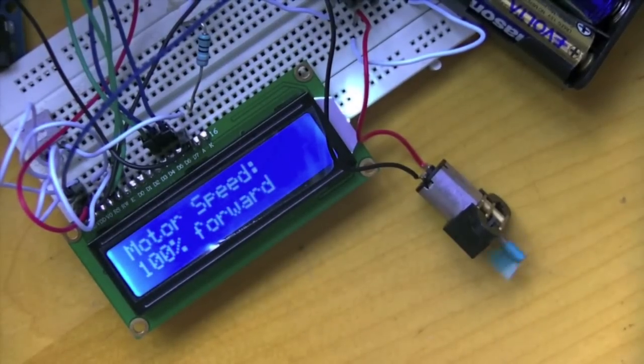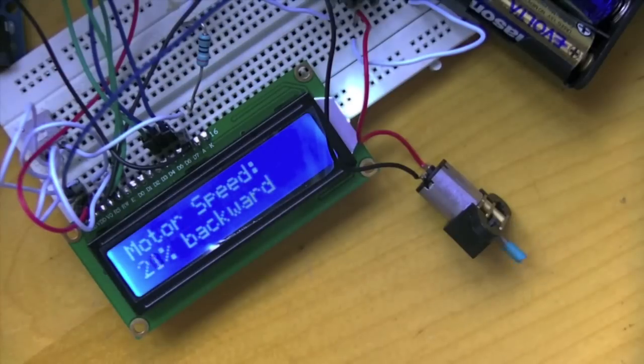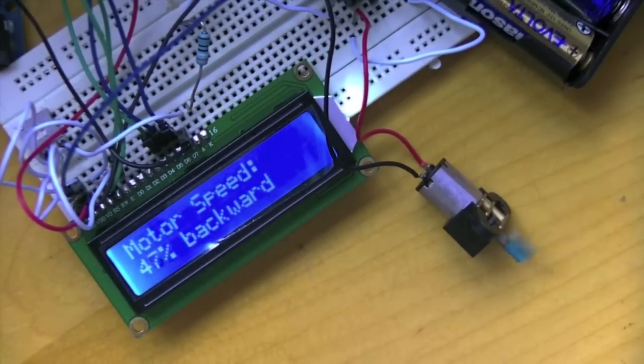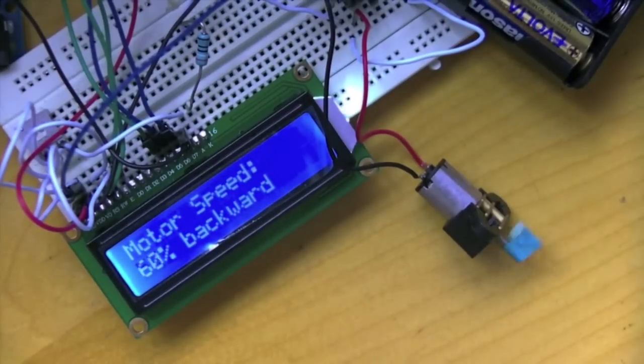And, let's see if it goes backwards as well. Yep, it's doing just what we thought it would. Going the other way. Again, it starts at about 30%. It takes about 30% to get enough torque to actually start moving.